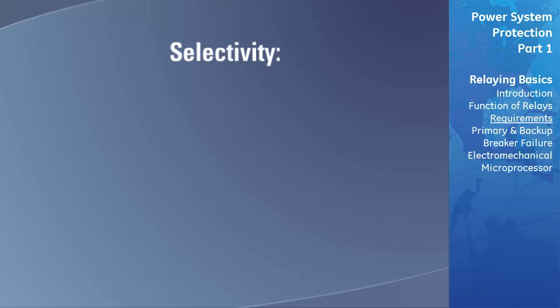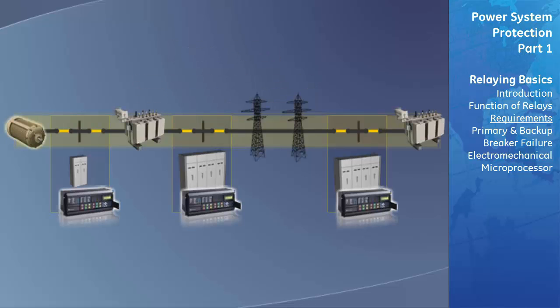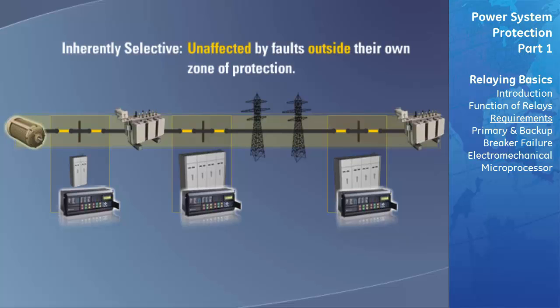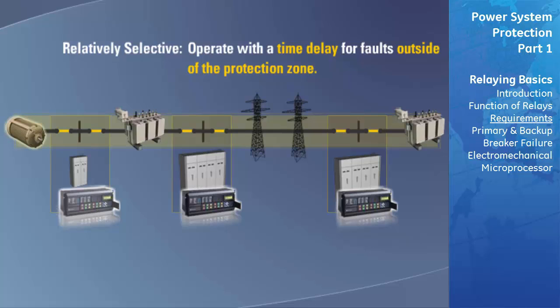The selectivity of a protective relay is its ability to trip the minimum number of circuit breakers to clear a fault. The relay must be able to select faults in its own zone of protection and ignore faults in adjoining zones. Some relaying schemes are inherently selective, that is, they are unaffected by faults outside of their own zone. Other types of relaying, which operate with a time delay for faults outside of the protected zone, are said to be relatively selective.